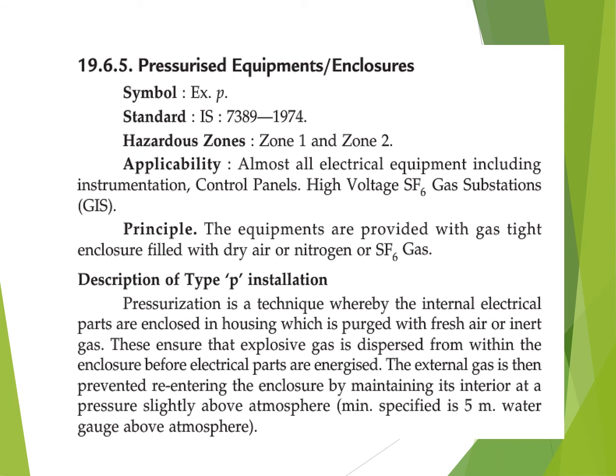Pressurized equipment is used in zone 1 and zone 2. Here the equipment may be covered and it is pressurized by using SF6 gas and so on. SF6 gas is an electronegative gas. So if any spark occurs in the equipment, this pressurized electronegative gas can clear it, or the spark will not come out from the equipment, and that area can be safe.